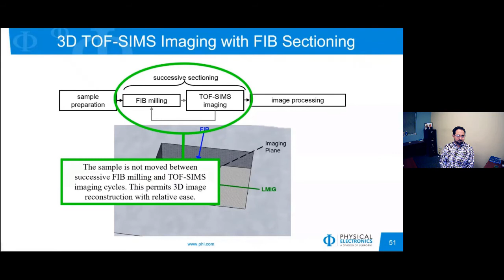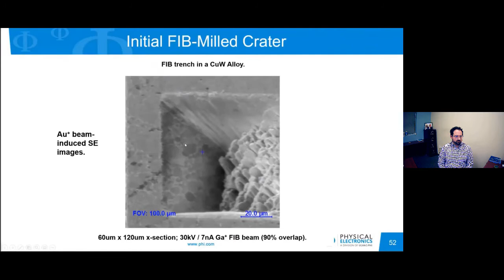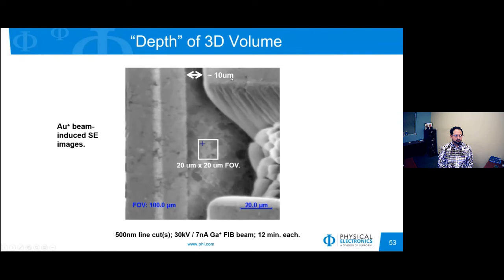and so just looking at the cross section of this FIB trench here, this is a 60 by 120 micron FIB trench, and this is a secondary electron image from the ion beam here, and so we want to find the area of interest here, and so we're going to look at this cross section here. And so that was before, and this is after. So the amount of material that's been removed is about 10 microns in depth. And so we chose a 20 micron by 20 micron field of view. So our field of view would be 20 by 20 by 10 microns. So this is a relatively deep depth profile that we're looking at here with this FIB-TOF image.